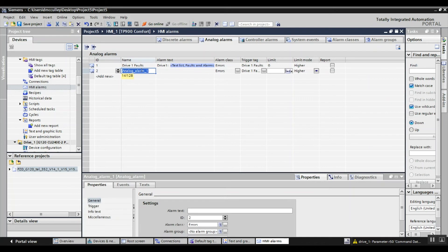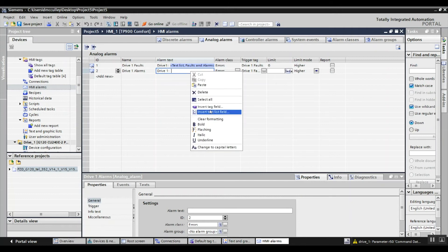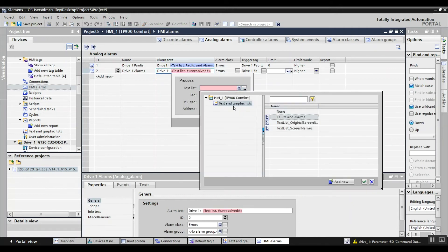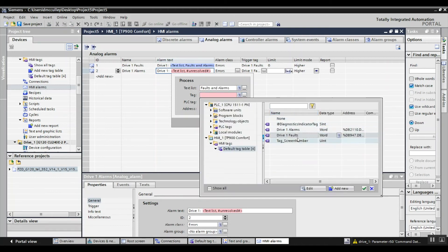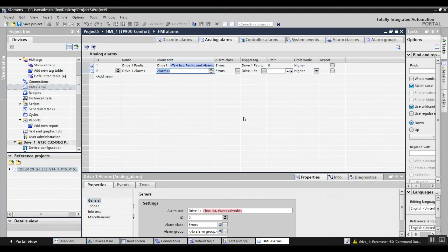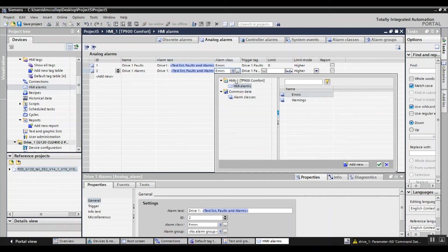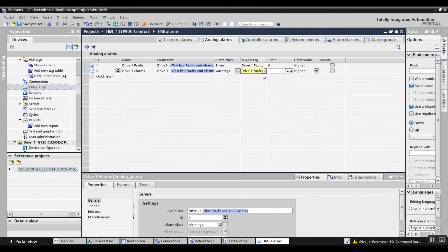Create another one: drive one alarms. Again, I want to see drive one semicolon space space, then insert text list — faults and alarms. This time we're doing the alarms. It's a warning class, so we're going to change that. And we're going to make it triggered upon the alarms tag with a value of zero or greater.